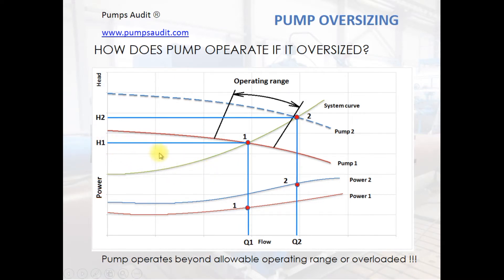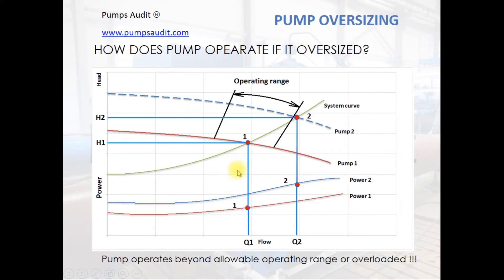Pump number one has appropriate parameters. If pump number one had been selected, the operating point would be number one, laying within the operating range. But pump number two has been selected. This pump has a higher head and the same flow. The operating point for pump 2 is point 2, and it lays outside the operating range in the area of overloading.